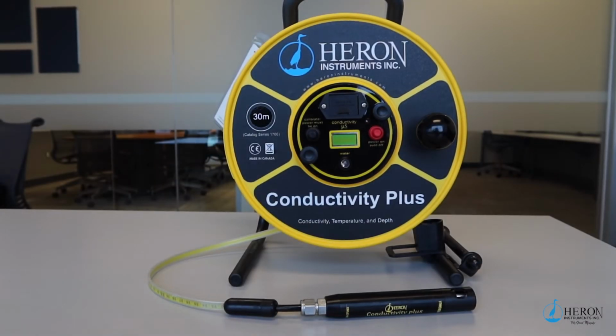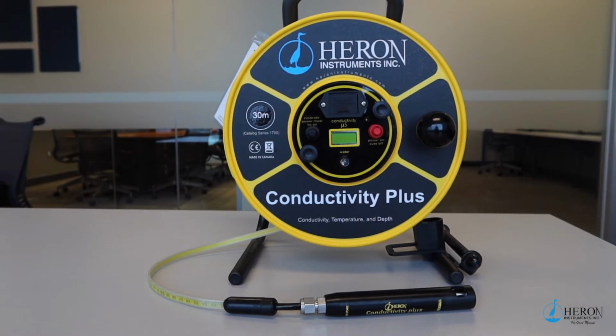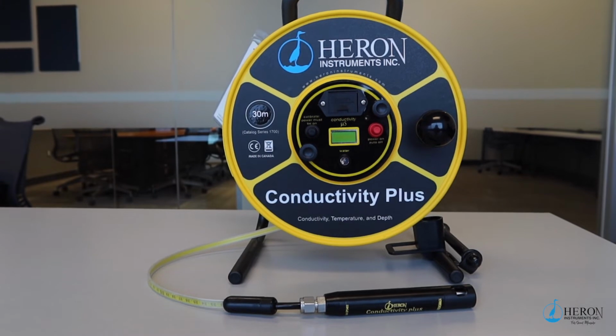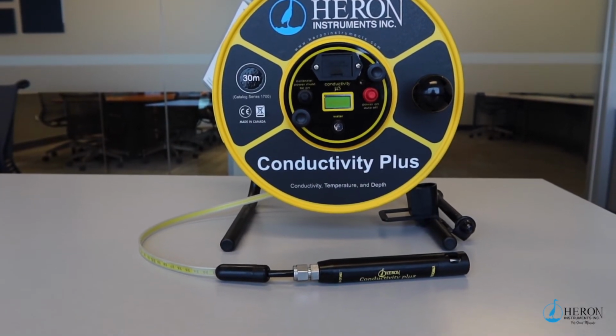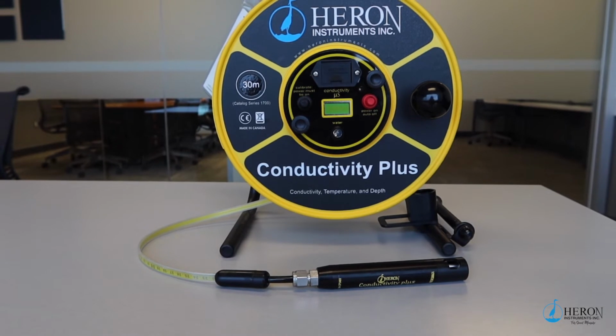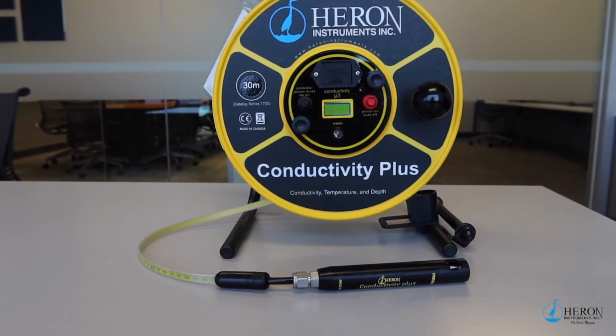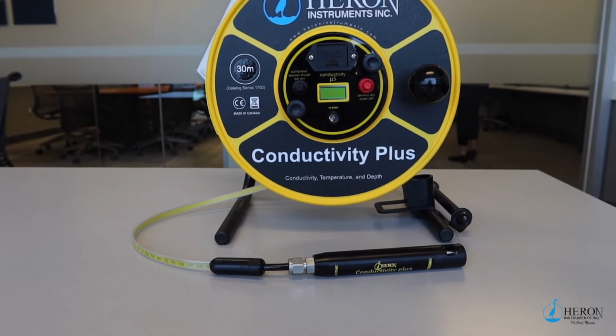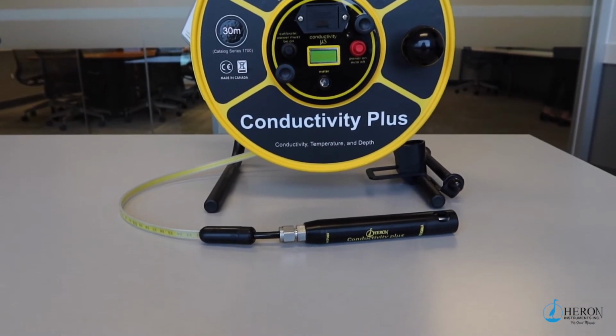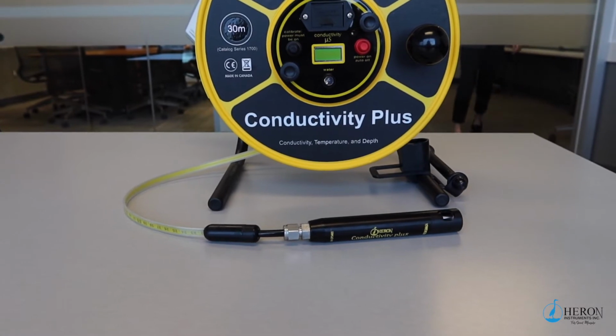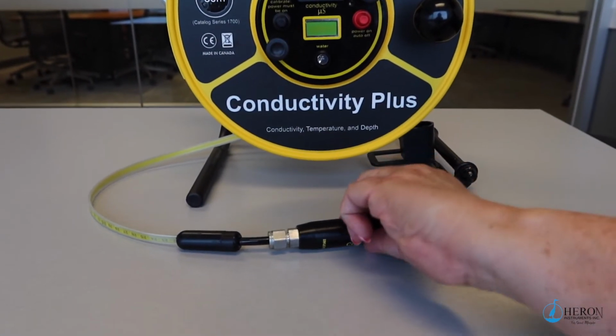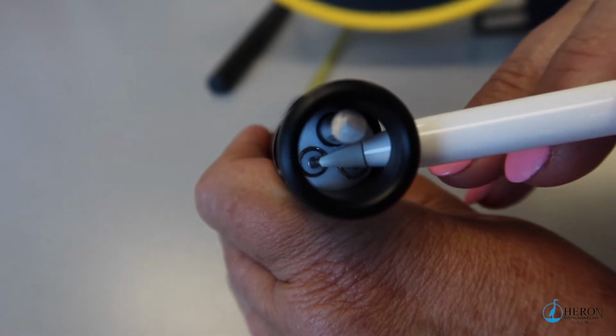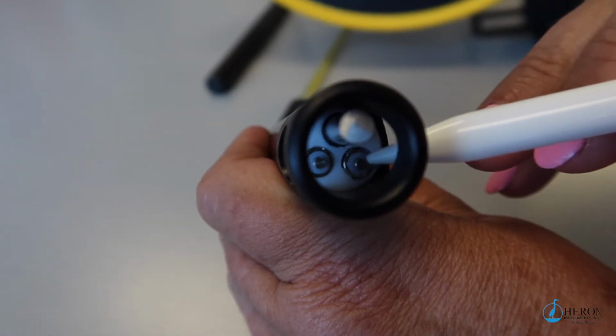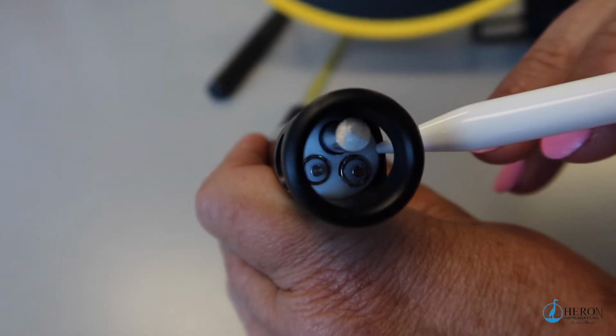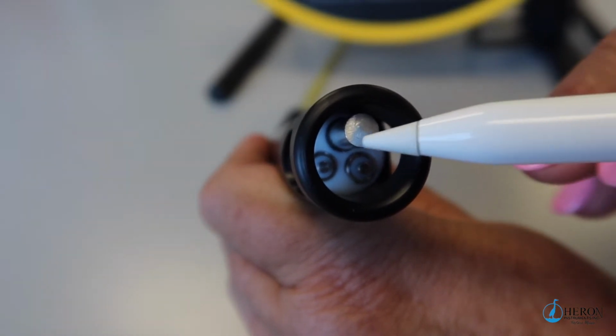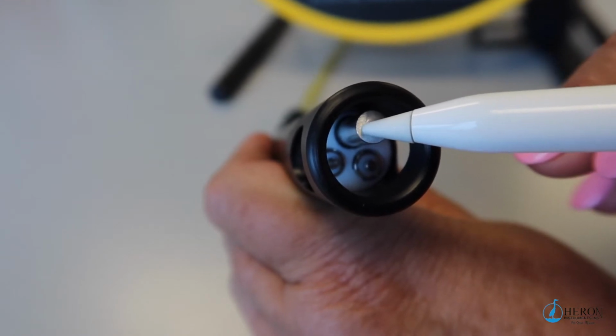The Conductivity Plus comes with a fully submersible, removable probe. This probe is used to detect water level, conductivity, and temperature. When you lower the probe into water, the unit will start to sound immediately. This will indicate the top of the water level, which can be read from the tape. Conductivity value will be shown on the display screen. Please note that on the probe, the white surface with the two rings needs to be fully submerged in water to obtain a signal. The 0 point starts here to the first foot or meter mark. The temperature sensor is located here.